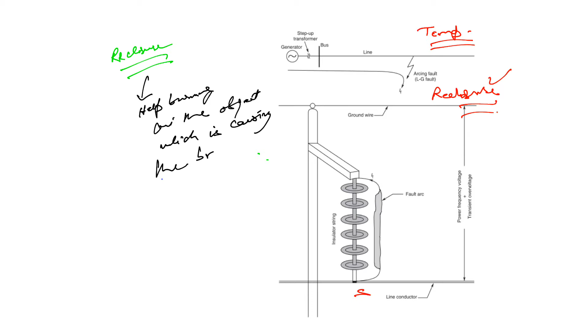You have observed sometimes at your homes also, whenever there is a fault, two or three times the supply goes on and off. This type of process is known as reclosing. So what is the function of the recloser? The recloser will help burn out the object which is causing the breakdown of the insulation.